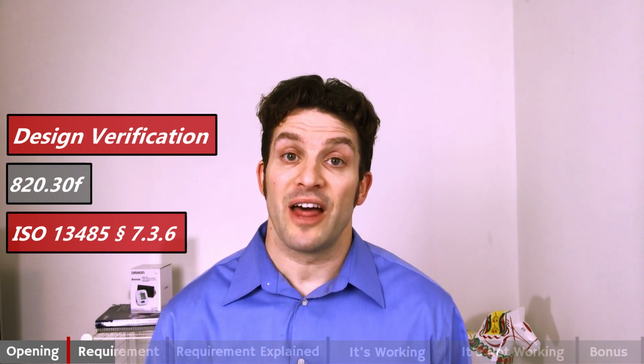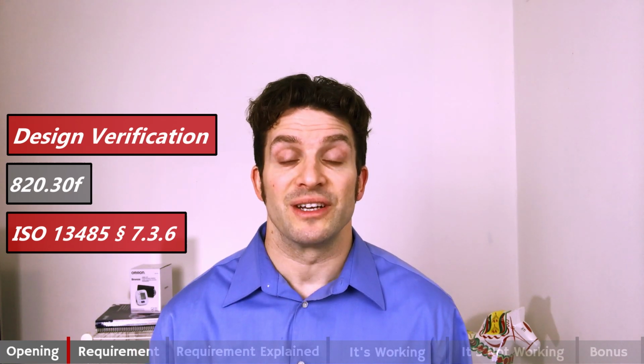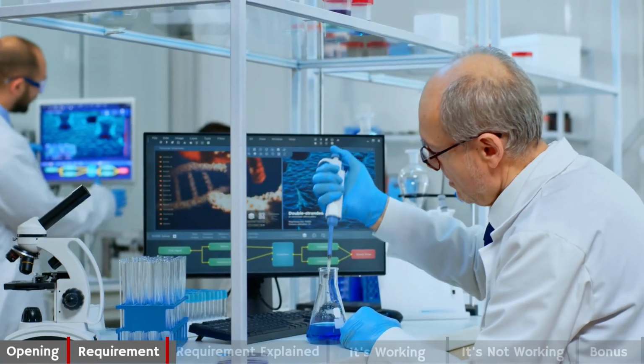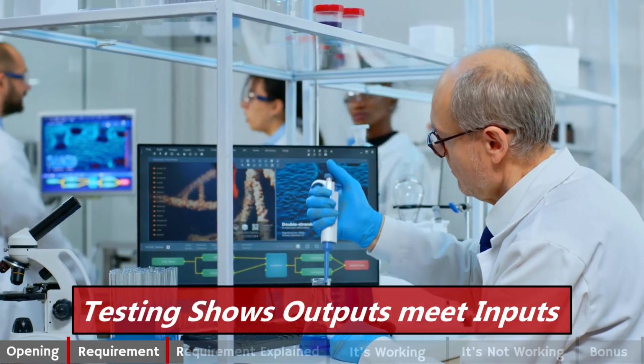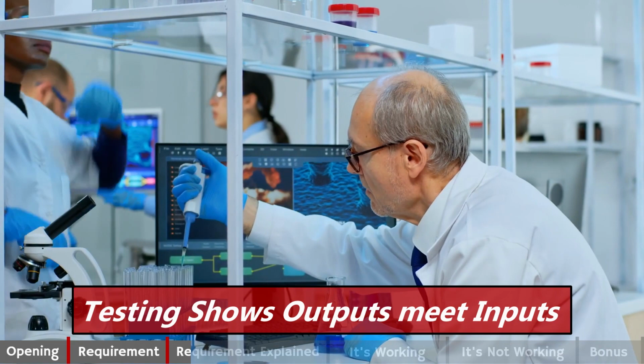Our requirement today, design verification, comes directly from 820.30(f) in ISO 13485 section 7.3.6. Design verification in 5 words. Testing shows outputs meet inputs.